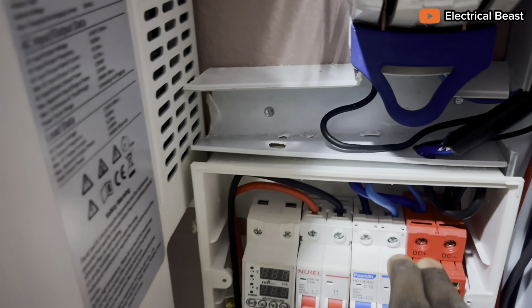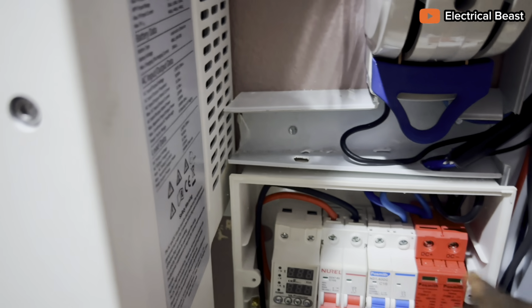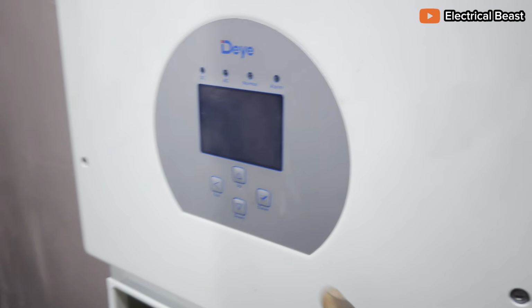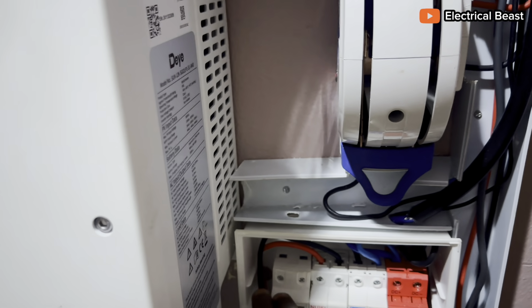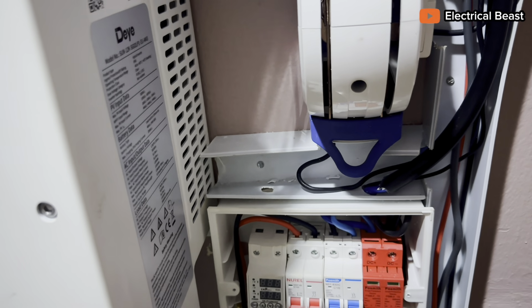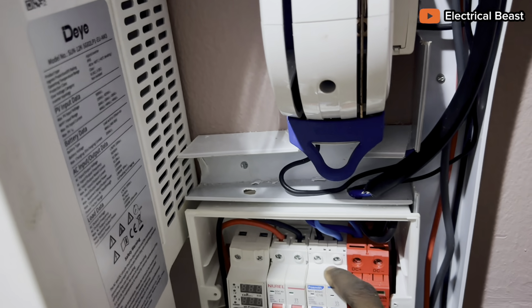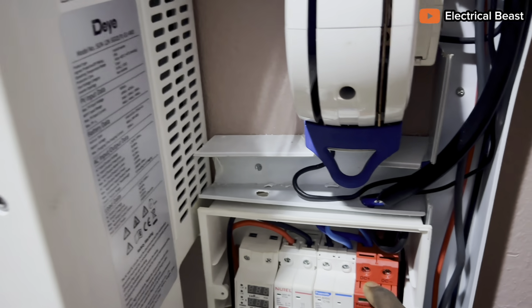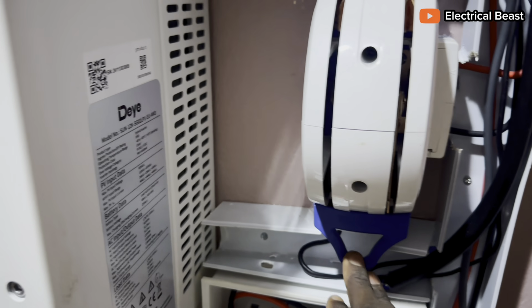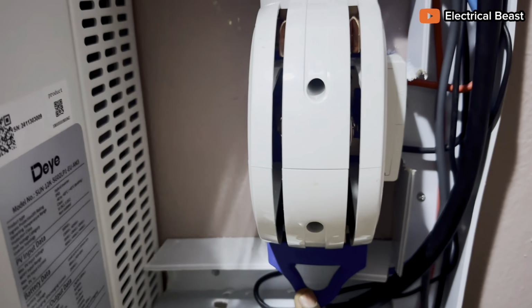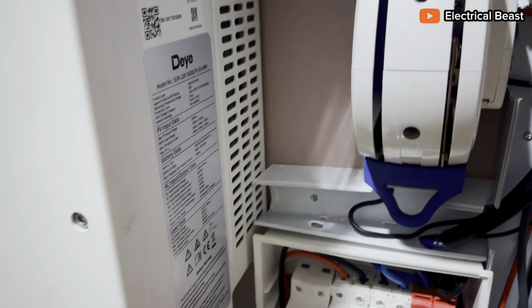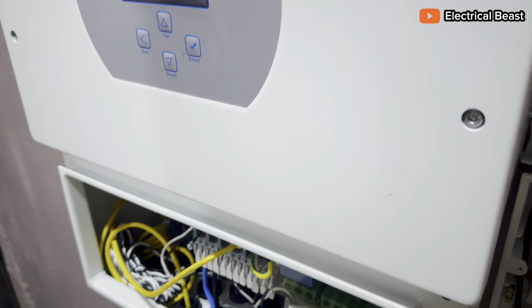I've connected everything, all the breakers. I'm not going to use the grid to charge these batteries with the inverter, and I'm not enabling grid charging for obvious reasons. The grid supply to this place isn't that good, and the generator they have here isn't too good either. But I've connected everything to this changeover, so there's no need for them to use the generator. They just bring this down, and if they want to use the inverter, they take this one up. But for charging the batteries through the inverter via grid charging, I don't want to enable that.